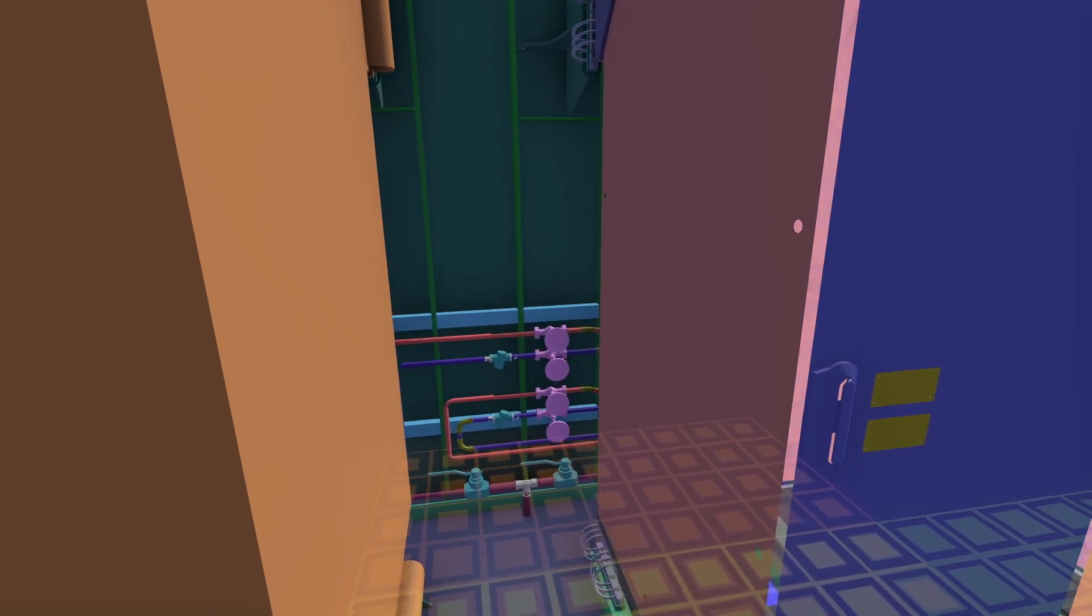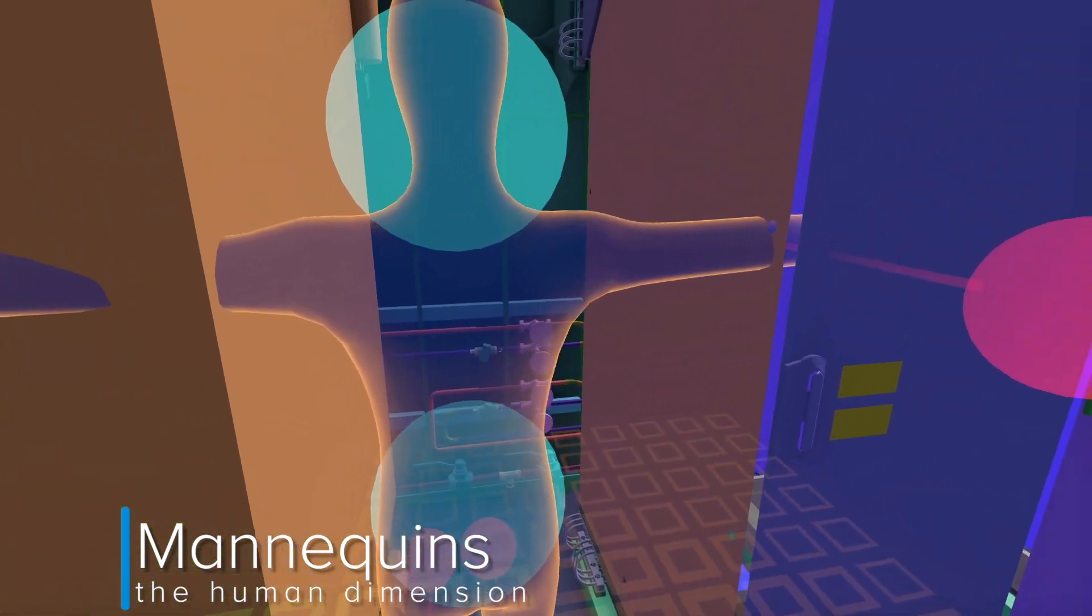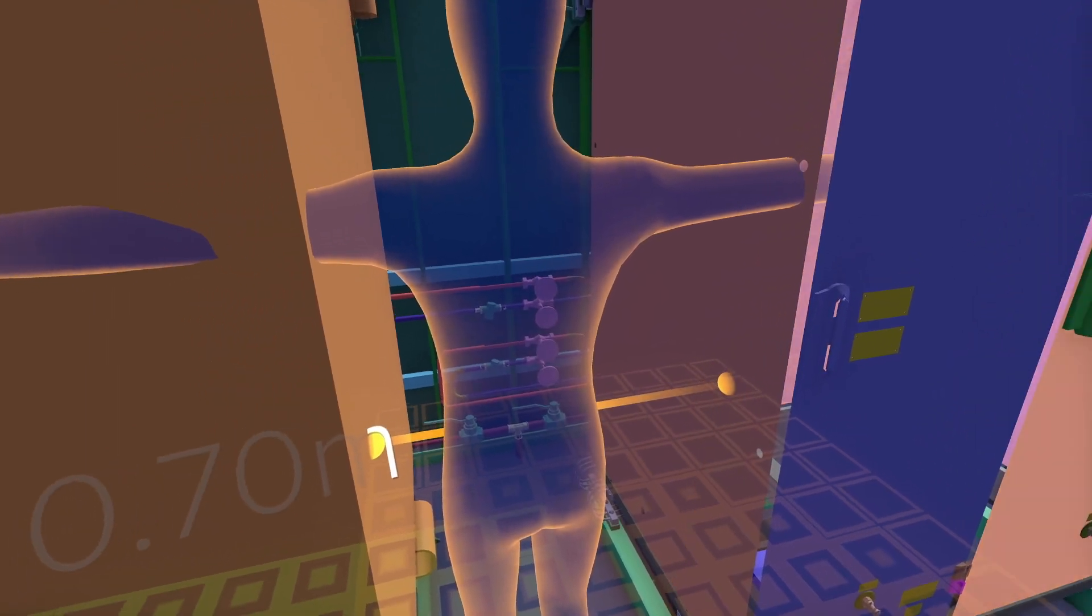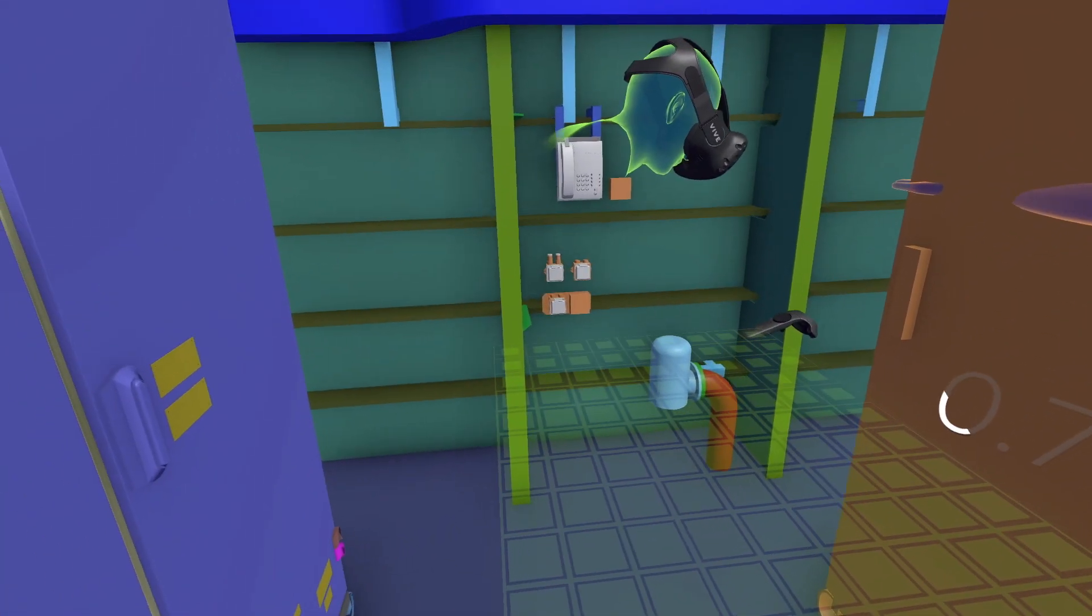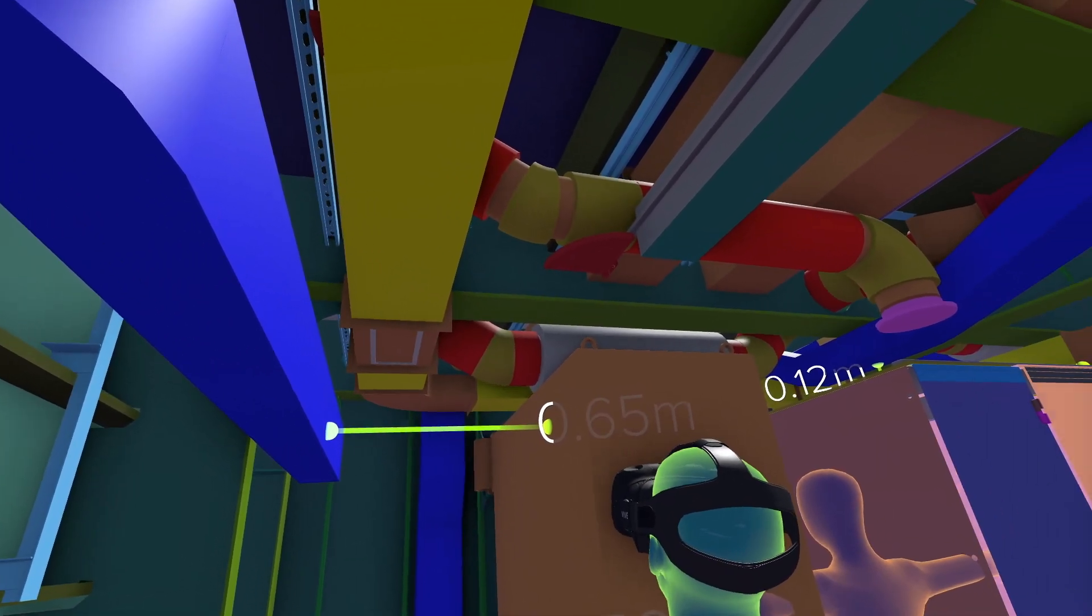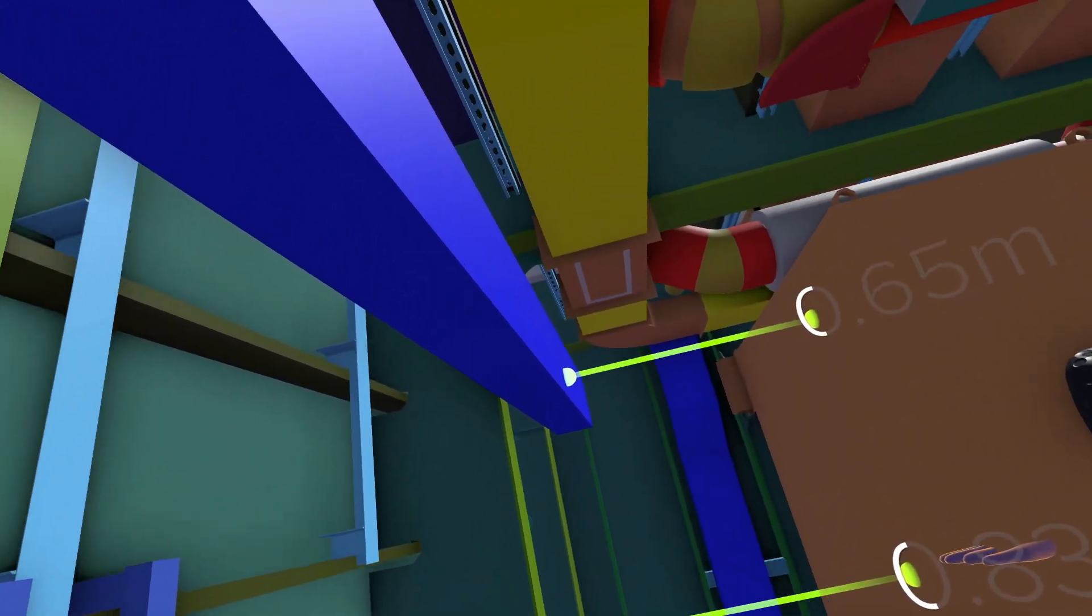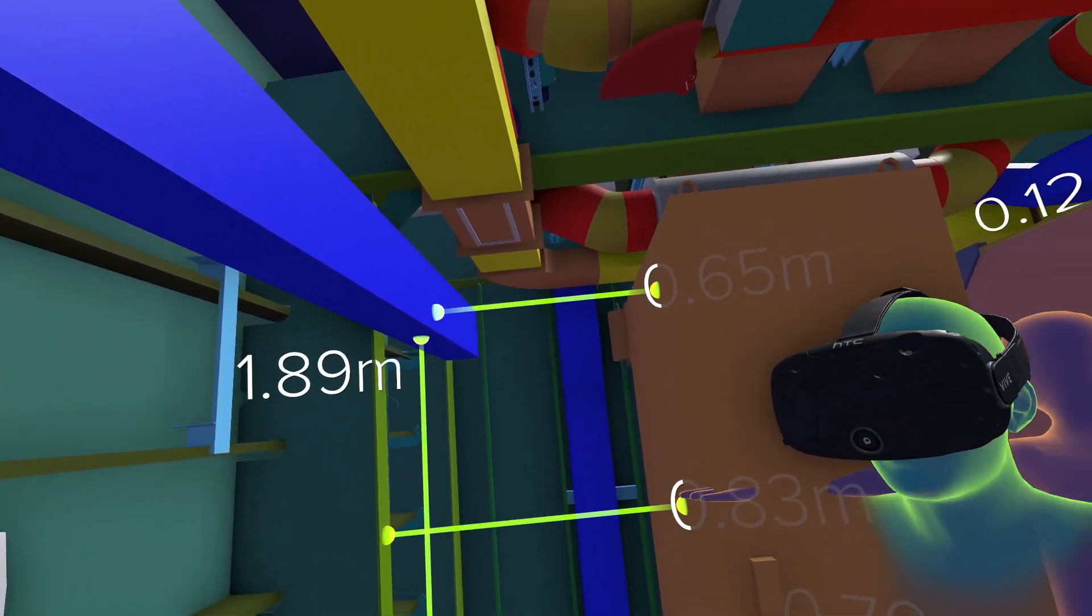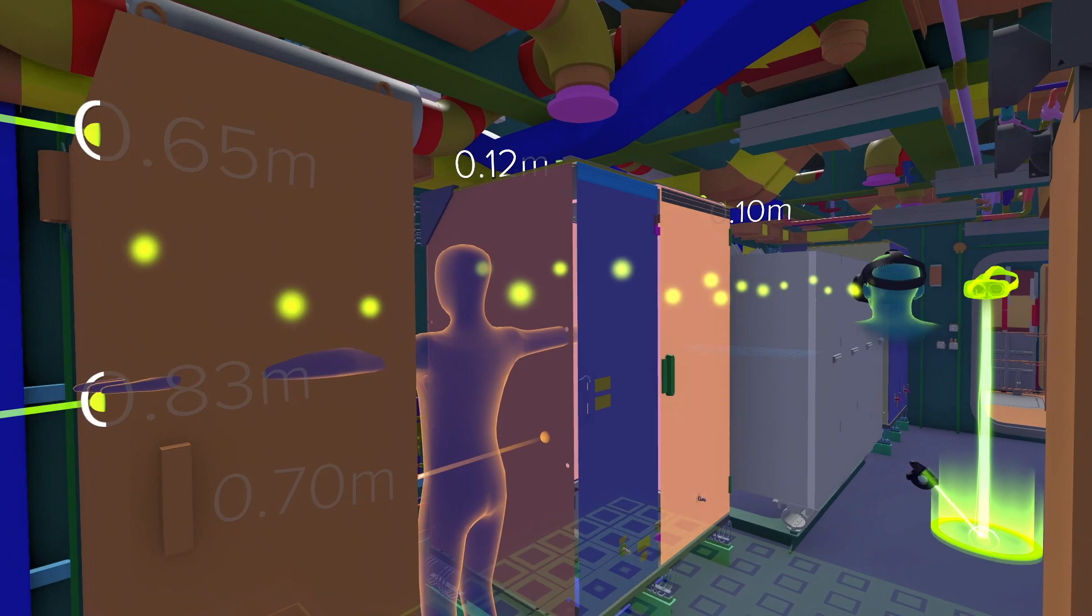Yeah, there's a lot of valves back here. We need to maintain this access way to those valves. Right. Well, how about this unit here? Are we able to move that across as well? Is there space over there? I'll have a look. Yeah. We've got 0.83 meters across, but up here, we've got 0.65. Hmm. Well, this isn't an access way. What's underneath the tray? Let's have a look. We've got 1.89 meters. That's fine. Cool. We can move both units across and maintain the gap for access to the valves.